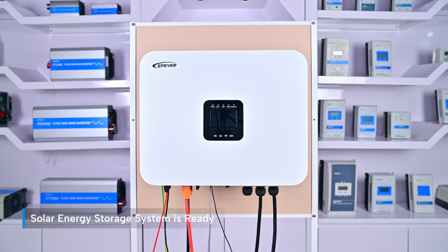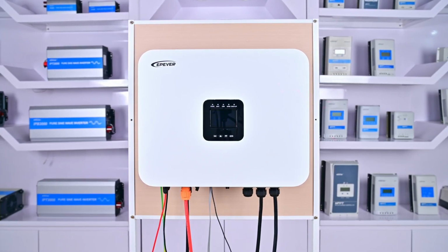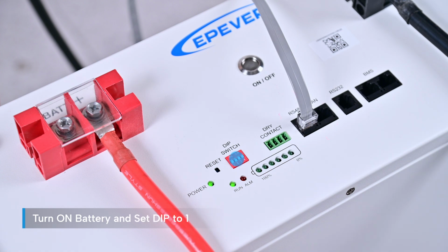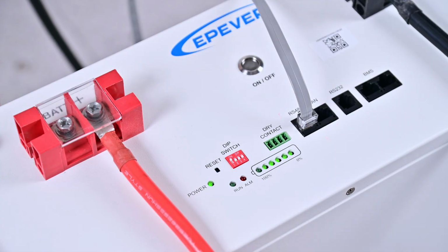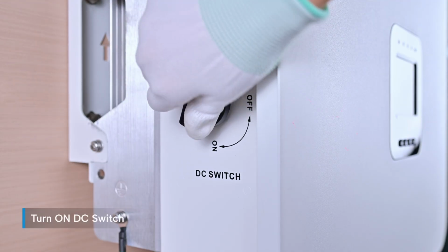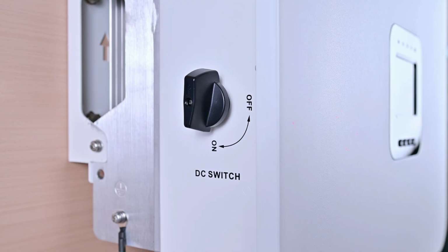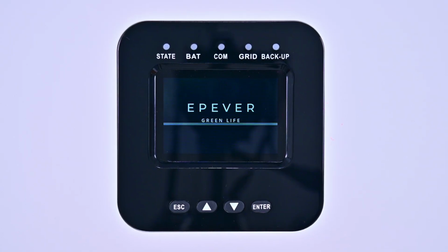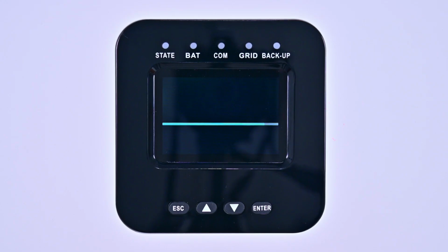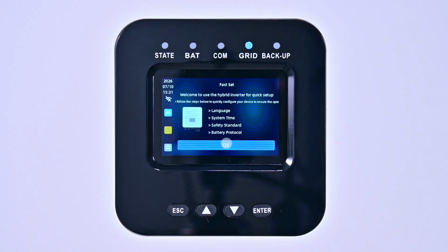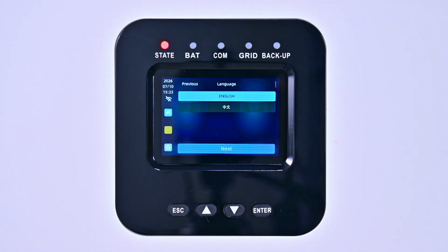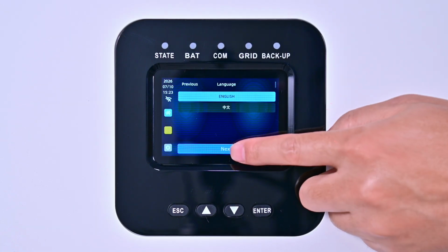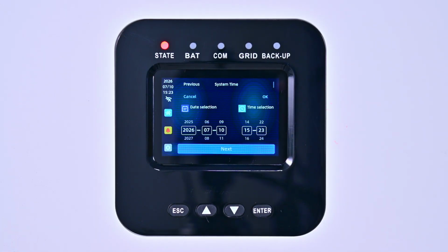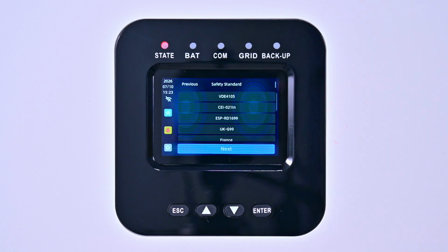After confirming that all cables are correctly and securely connected, turn on the battery and set DIP switch 1 to the on position. Then, turn on the DC switch on the left side of the ELS. Waiting for the device to initialize. When a brand new ELS is powered on for the first time, it will enter the quick setup screen. Keep the default system language and next. After confirming the time is correct, proceed to the next step.